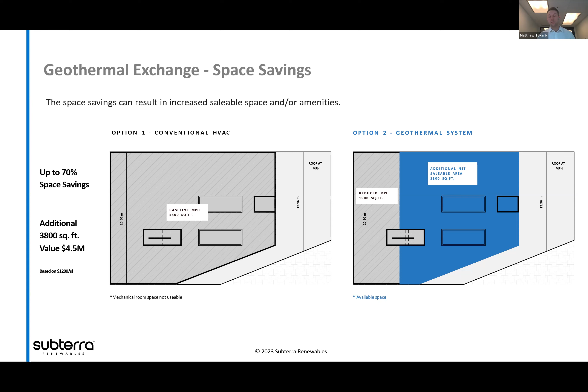When we're talking about space savings, that translates into dollars in the real estate folks' minds. You can do a couple things with that: get outdoor amenity spaces, which gives more enjoyment and value to the building, but generally we often find building developers can get more rentable or saleable space. If you're a condo developer thinking about saleable space on a penthouse level, you can sell that space for $1,200 to $1,500 in downtown Toronto per square foot. So every square foot saved by reducing that mechanical penthouse can be really impactful and valuable from a dollars and cents standpoint.